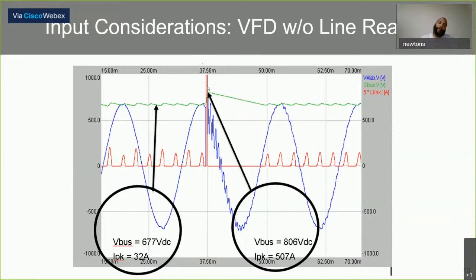At the moment where the capacitor bank closed into the circuit, whether it's due to power quality or some type of voltage sag, whatever caused or initiated that capacitor bank to close, you can see at that moment the DC bus voltage jumped up to 806 volts DC, and the peak current snuck up to 507 amps. So this is very significant because, as you can see, the peak current went more than 10 times the nominal rate that the drive is used to seeing.